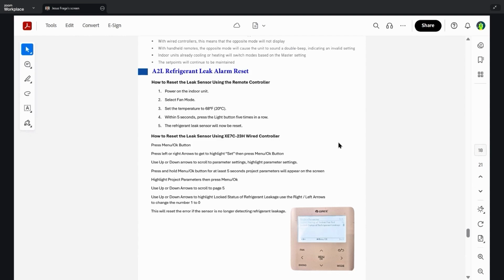Below is how to reset it through the XE7C23H wired controller. It's a similar process. You just press the menu and OK button, which is the same button, it's just the designation on the controller as you see below. So what you can do is press left or right keys to highlight set, then press menu / OK. Press up or down buttons to scroll to parameter settings. Highlight parameter settings, press and hold the menu OK button for at least 5 seconds, and the project parameters will appear on the screen.